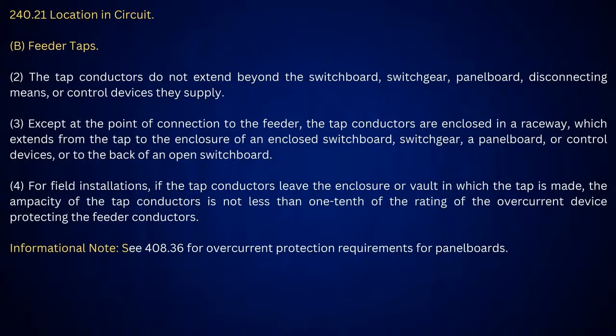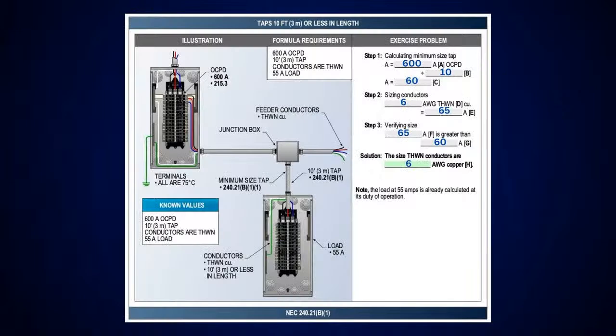Okay. Just to prove this, here's your calculation. It's very simple. We've got a 600 amp upstream, divide by 10 gives you 60 amps. I go over, look at table 310.16, come down the 75 degree column, pick up 60 amps. It'll tell you need number 6. Now that 60 amps is the minimum. I can go all the way up to 600, but once I get to 600, it's no longer a tap at that point. But anything from 60 amps up, I can tap off of that feeder.